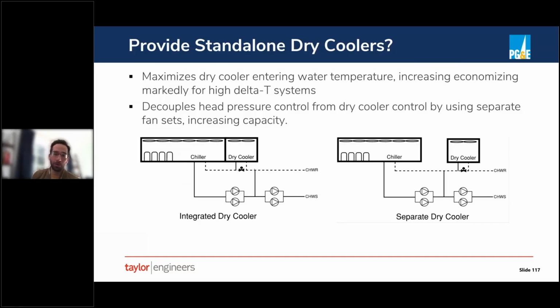If this were a primary only system, the same consideration would apply, but it'd be where the dry cooler is connected relative to the minimum flow bypass. Because once you get below minimum flow in a primary only system, which can be fairly high for air-cooled chillers, you effectively run into the same constraint that you would for a primary secondary system with constant speed primary pumps. So the issue here is that in these integrated systems, there's a risk that you're diluting the return water temperature that's going into the dry cooler.